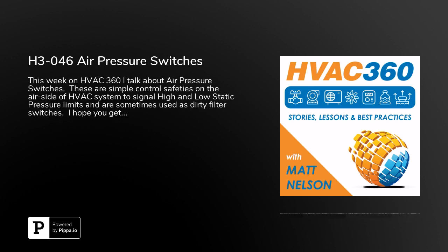And a lot of times, if you rely on the static pressure sensor, even if everything goes normally to plan, sometimes your VFD is not going to react that fast, and you're kind of exceeding that set point. So the high limit and the low limit provide a quick response to a change in the static pressure, just to protect that ductwork.